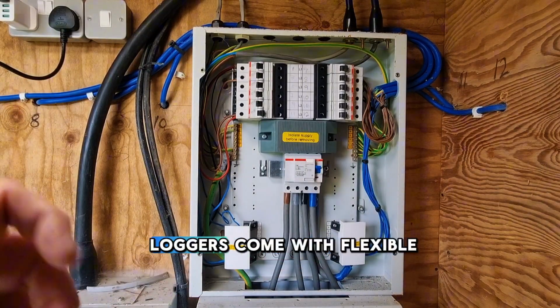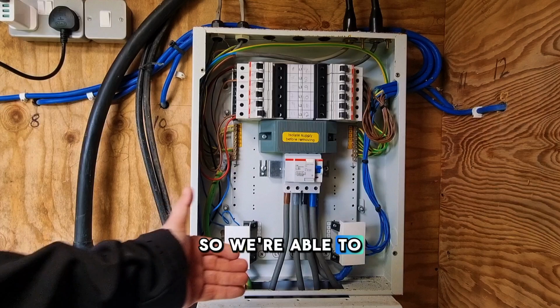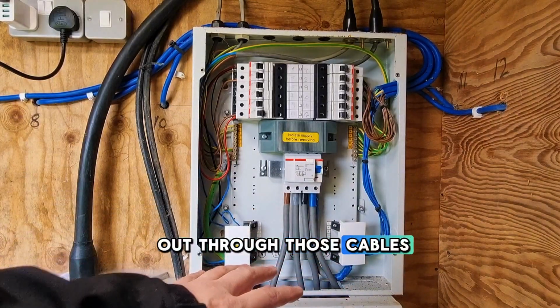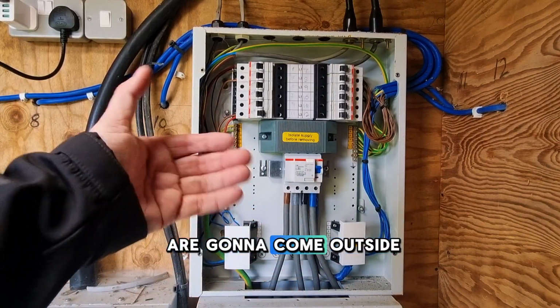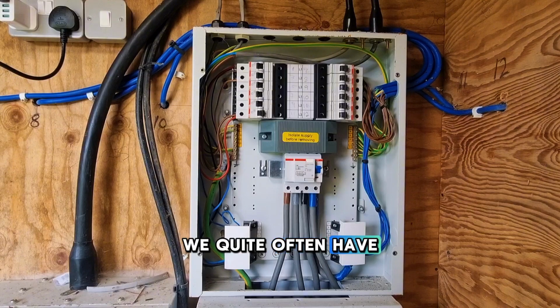Most of our energy loggers come with flexible leads, so we're able to fish those in and out through those cables. But because those cables come outside of the cabinet, we quite often have to either leave a cabinet cover off, or be in a position where we can put a temporary cover across the board and have an access out to our logger, our energy meter.